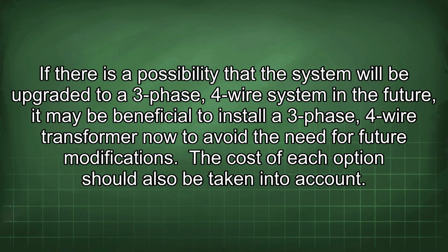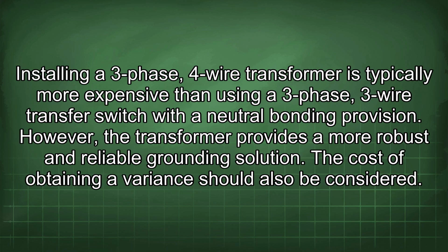If there is a possibility that the system will be upgraded to a three-phase, four-wire system in the future, it may be beneficial to install a 3-phase, 4-wire transformer now to avoid the need for future modifications. The cost of each option should also be taken into account. Installing a 3-phase, 4-wire transformer is typically more expensive than using a 3-phase, 3-wire transfer switch with a neutral bonding provision. However, the transformer provides a more robust and reliable grounding solution.